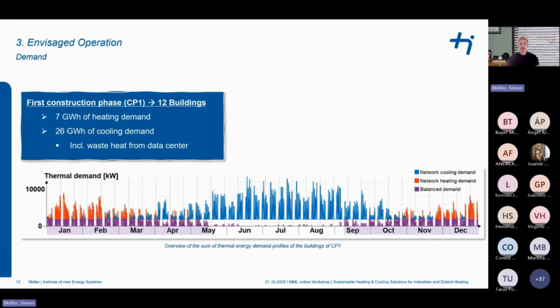This is the case when one of the buildings connected to the network has a heating demand and another building, because of its function or utilization, has a cooling demand at the same time. So at the end of October, for example, the data center with its cooling demand will eject heat into the network via heat exchanger. And on the other end of the network, some office buildings with heating demands will extract some heat via the heat pumps.